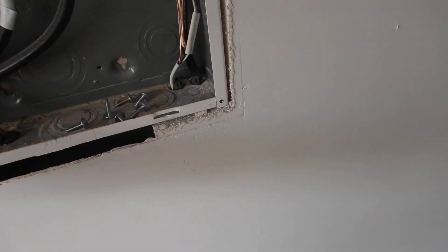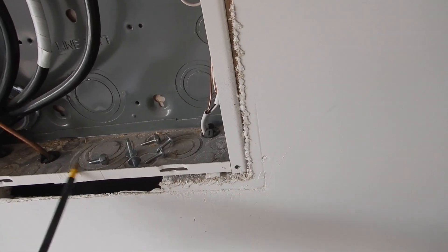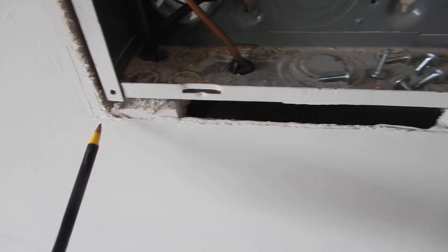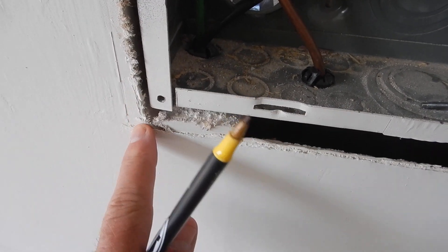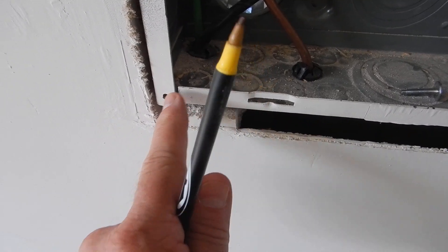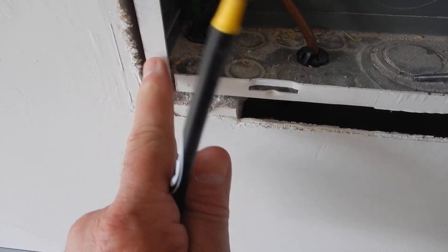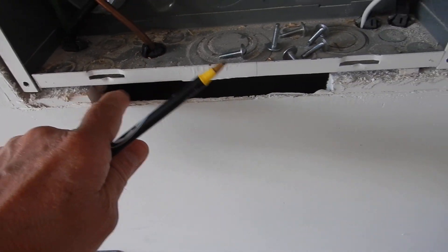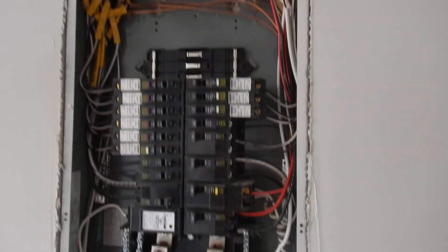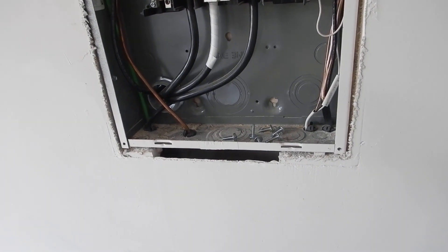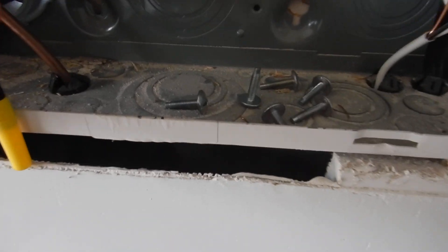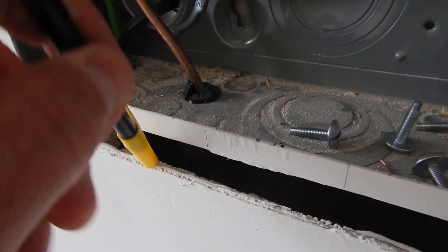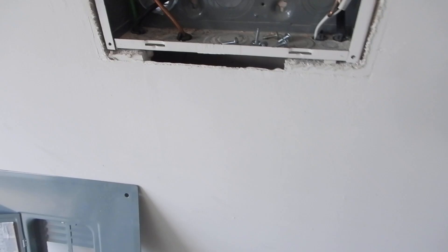Come along here - we're not supposed to have more than a sixteenth of an inch gap between the cabinet and the wall. Let's see. This cover fits right on top of here, check this out. See this edge? The cover's supposed to reach the edge, so now we've got some distance here, and even more distance here. The reason being, if this panel or cabinet melts down in a fire, it'll just go right through here, wrap around your walls and go on up. You got a bad day for sure.